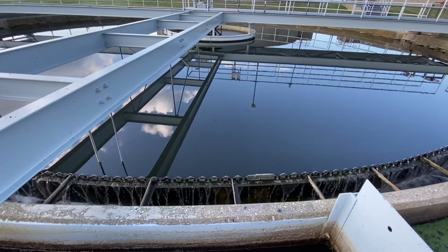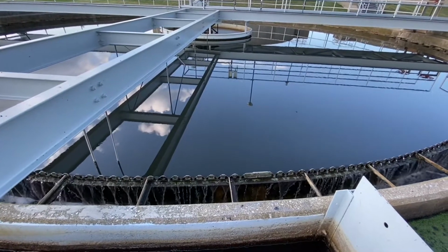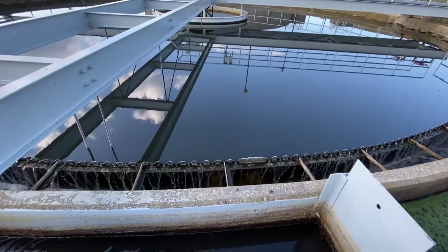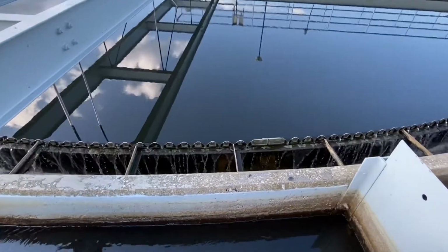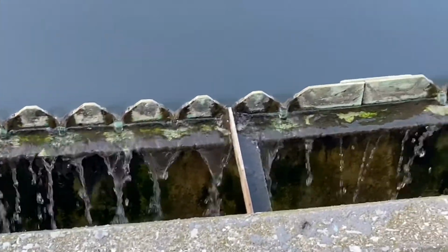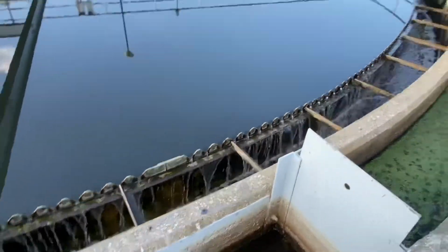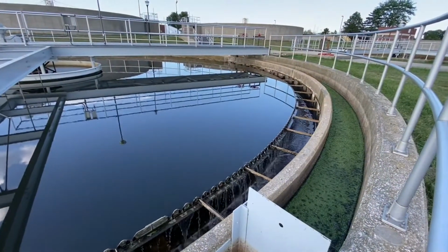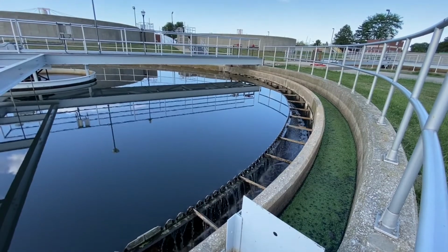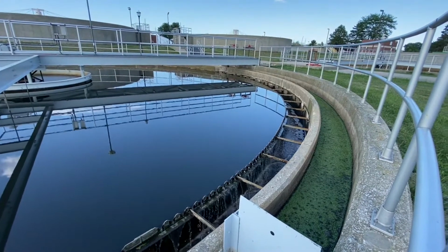The water carrying the coagulated particles then flows into a clarifier where detention time is given for the particles to settle down to the bottom in the form of a sludge being pumped out of the tank, removing the phosphorus from the water to a different point in the treatment process. Then only the clear water, the effluent water, comes over the weirs and exits the treatment process, removing the phosphorus levels down to the required levels of less than 1 milligram per liter or 1 part per million. Now that was some good looking floc.